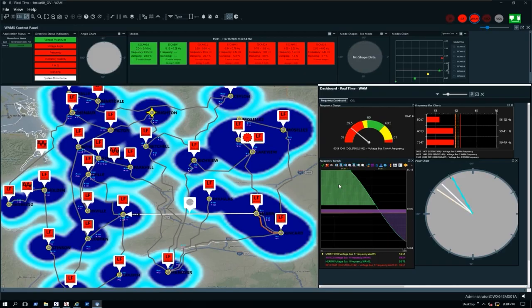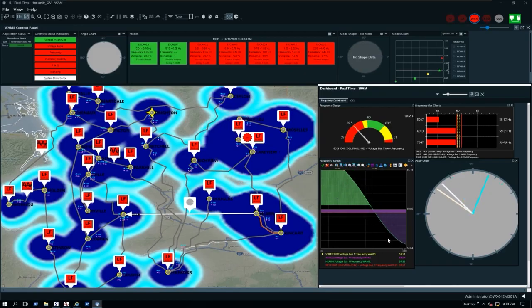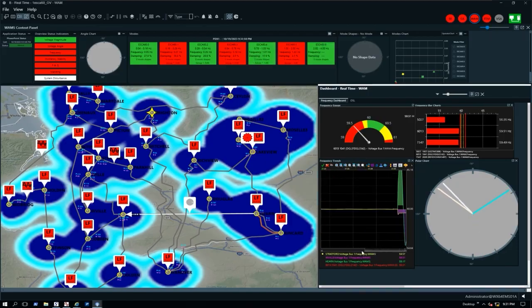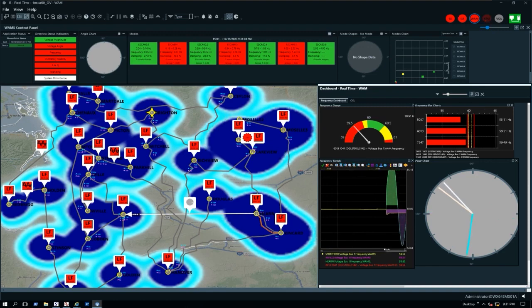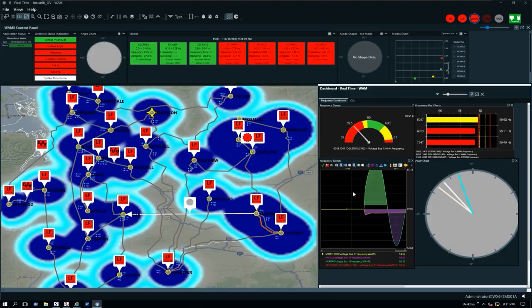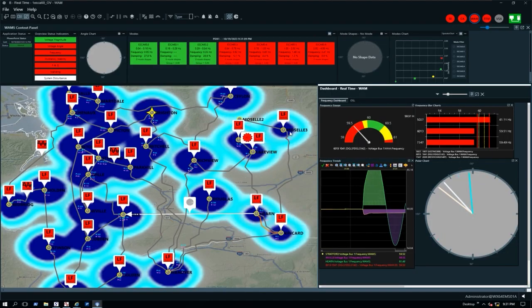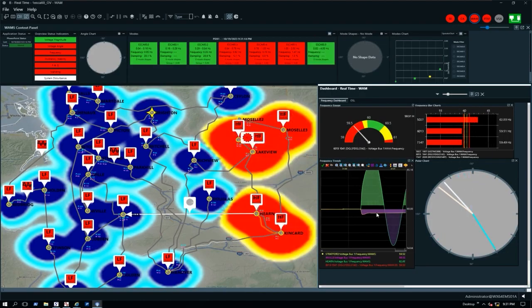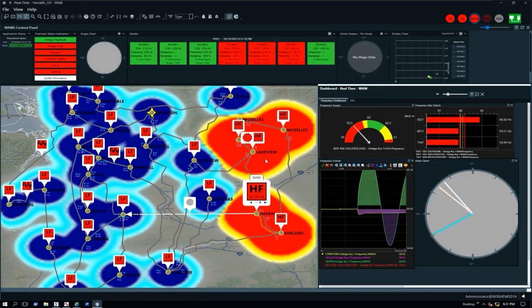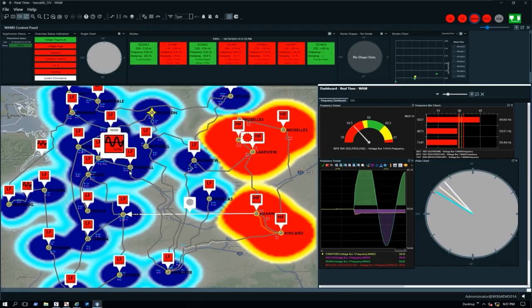So then our large or small island is now rapidly swinging back and forth due to that mismatch of generation and load. I'm going to adjust the timing scale here just so it's a little easier to visualize. But the two islands are going to swing back and forth against each other. We've got some polar charts that show the smaller island's frequency is rapidly changing compared to the larger island. So there are some things that we could do as an operator.